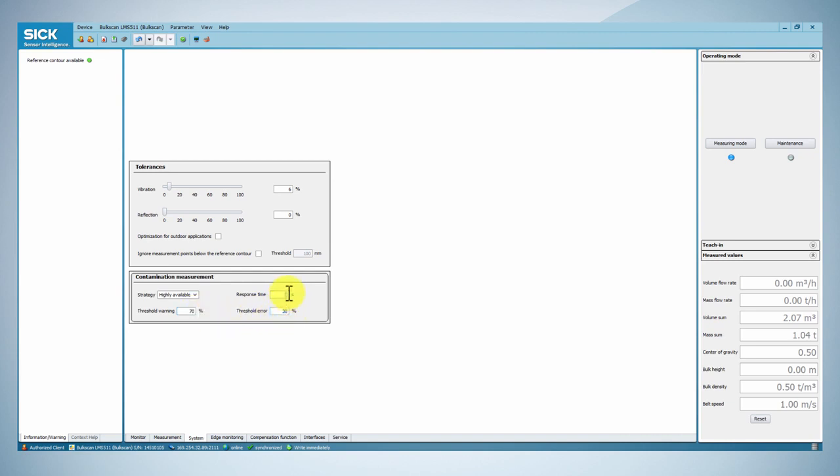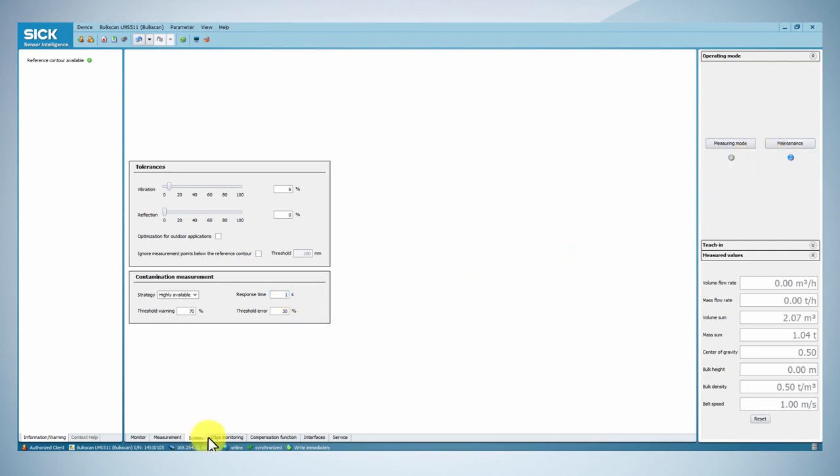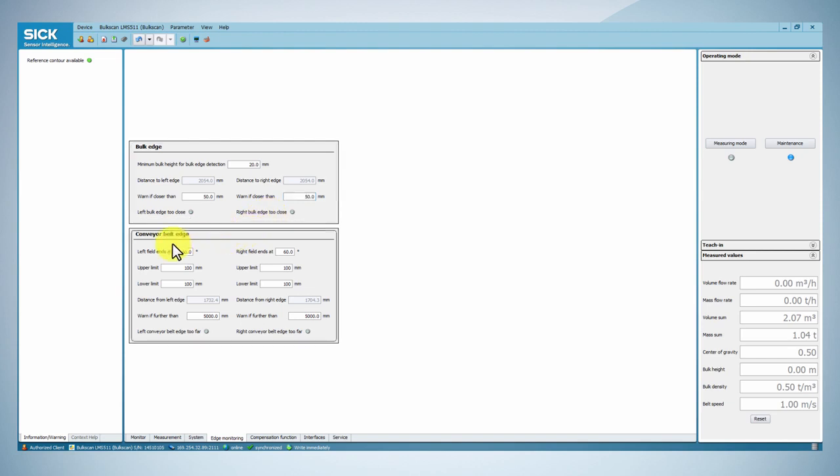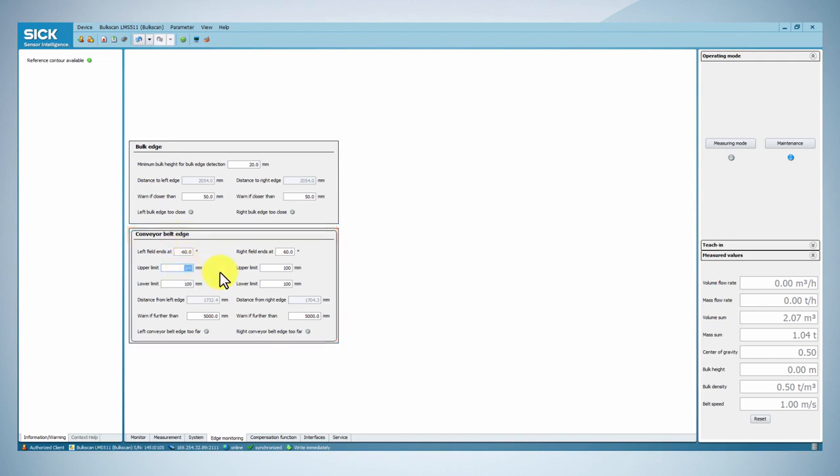If you wish to monitor the position of the bulk material on the conveyor belt, you can go to the Bulk Edge tab Setup Warnings in order to prevent the material from falling out of the belt. Furthermore, you can monitor the position of the conveyor belt outside of the measurement area by setting up warnings. This can help to avoid damages due to the belt slipping or tilting.